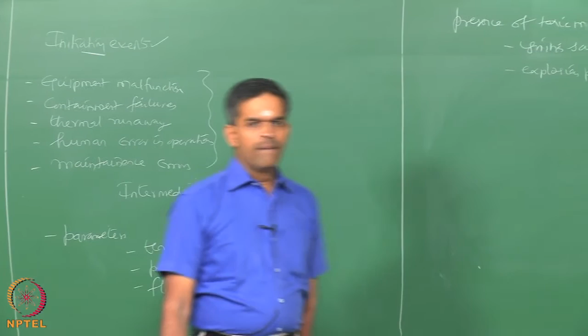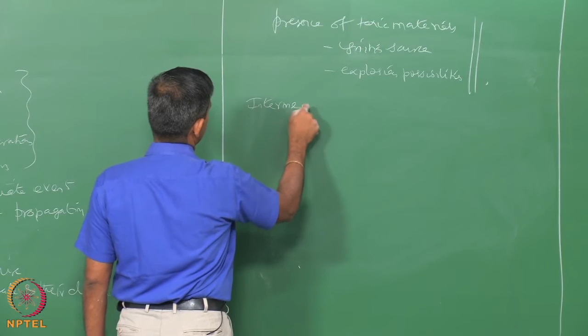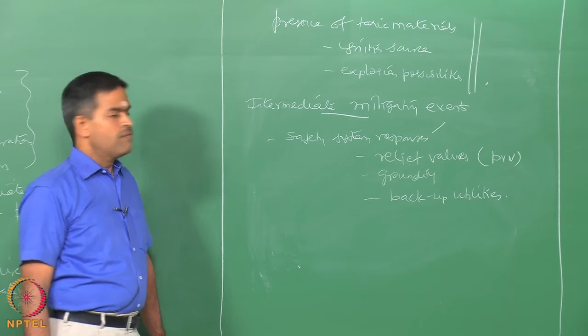Of course, we all agree and we know, because you may be asking a question here. So, we in the offshore industry or in the process industry, do we have any control mechanisms which are designed as a part of the system which can control either the initiating or the propagating events? The answer is yes. There are intermediate mitigating events. Let us quickly see what they are. We can say safety system responses. Some examples can be given here: relief valves, let us say PRV, pressure relief valves, grounding, and backup utilities. We have power backup utilities in case of uninterrupted power supply, in case of external DG sets, etc. All these can be identified as safety system responses. We also have mitigating system responses.